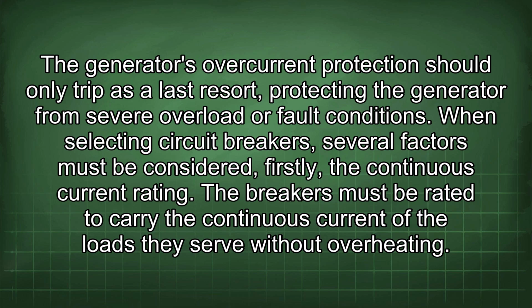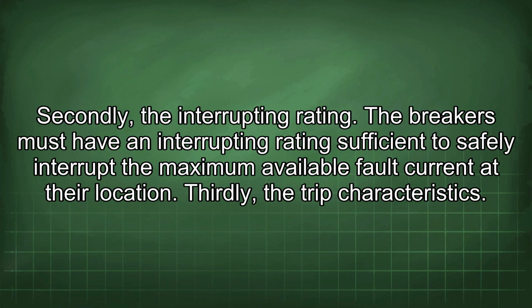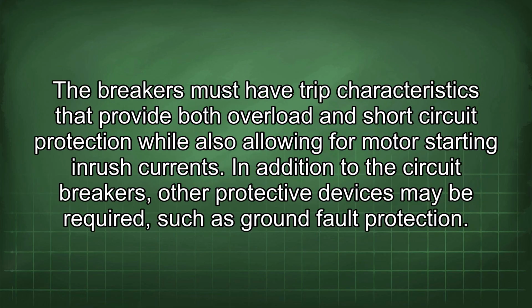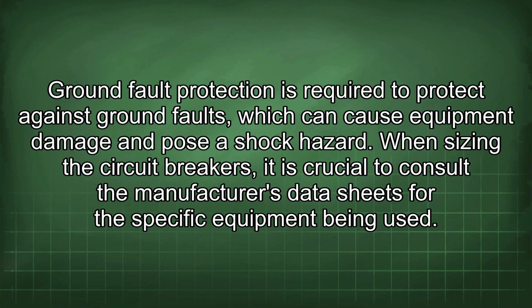When selecting circuit breakers, several factors must be considered. Firstly, the continuous current rating. The breakers must be rated to carry the continuous current of the loads they serve without overheating. Secondly, the interrupting rating. The breakers must have an interrupting rating sufficient to safely interrupt the maximum available fault current at their location. Thirdly, the trip characteristics. The breakers must have trip characteristics that provide both overload and short-circuit protection while also allowing for motor starting inrush currents. In addition to the circuit breakers, other protective devices may be required, such as ground fault protection. Ground fault protection is required to protect against ground faults, which can cause equipment damage and pose a shock hazard.